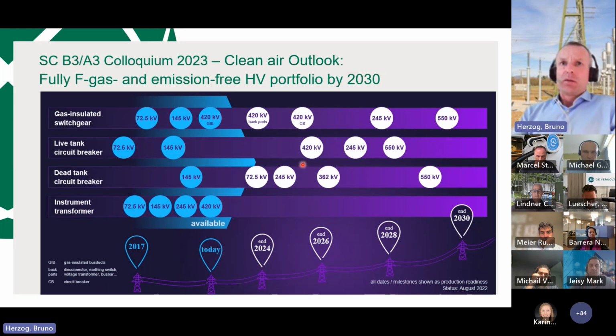And then we go as well with the dead tank breaker, and later on, mainly for Switzerland, it's interesting to have this for 245 kV. As you know, Swissgrid uses this level for most of its substations, so we should be able to follow up there by the beginning of '28. So this is our roadmap, how we see the future for clean air technology, fully F-gas free, and we are really looking forward to supporting the demand on the market for this application.